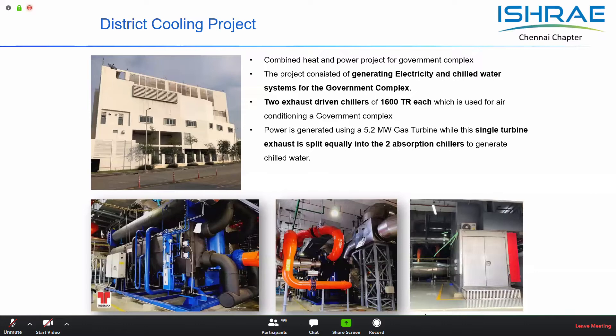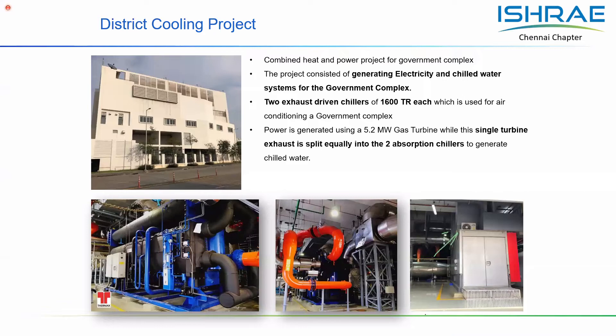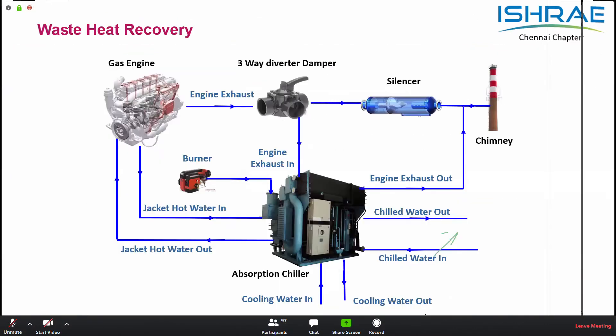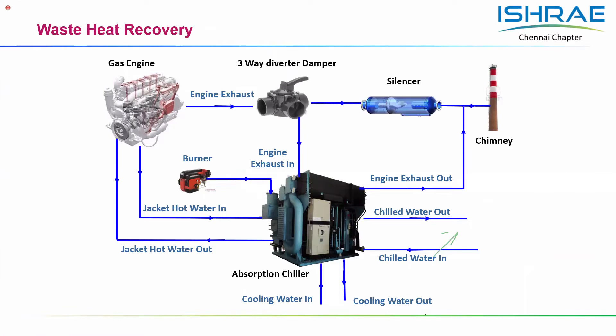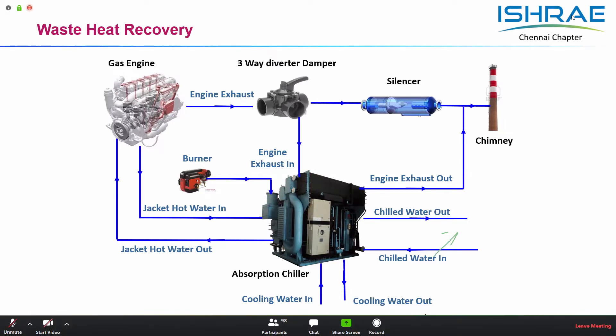Such projects are very well established. An engine-based heat recovery system includes the engine, a three-way diverter valve to control the flow of exhaust gas into the chiller, and can make use of engine jacket water as well. There can be a provision to fire natural gas directly so that in the absence of engine operation, or when the exhaust gas or jacket water has low heat value due to part-load engine operation, we can still achieve the full heating or cooling requirement by firing natural gas.